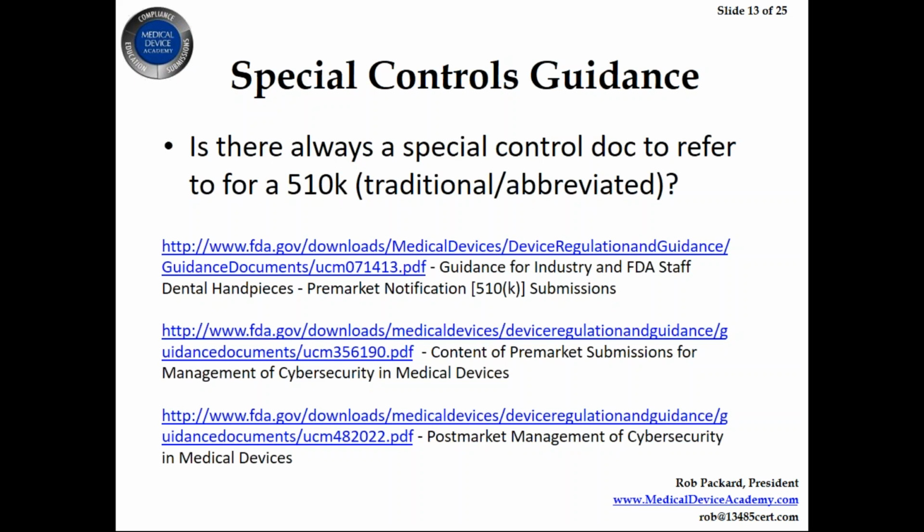I was doing my first needle submission, and I wasn't aware that the FDA has a separate guidance document for needles, and it wasn't listed under the 3-letter product code, which is where it should be. It wasn't listed in any of the previous submissions that I was looking at as predicates, and because this seemed like a very straightforward submission, I didn't expect the FDA to have a guidance document I wasn't aware of. But they made me aware of it after we submitted, and we had to do some additional testing. So that's another example of why it really pays to do a pre-sub meeting.